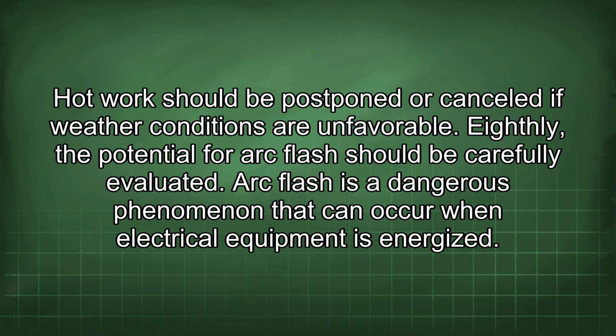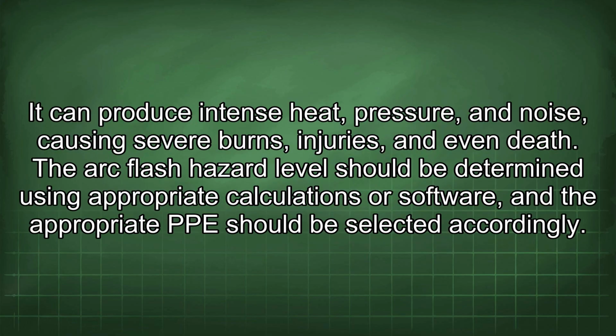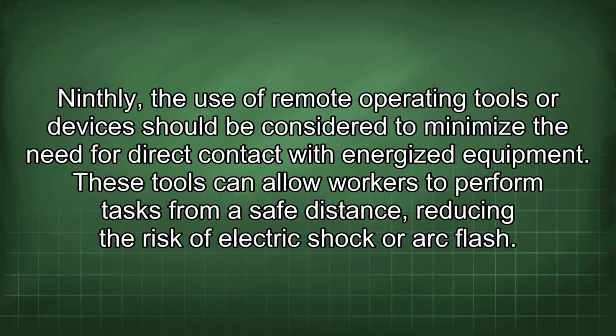Eighthly, the potential for arc flash should be carefully evaluated. Arc flash is a dangerous phenomenon that can occur when electrical equipment is energized. It can produce intense heat, pressure, and noise, causing severe burns, injuries, and even death. The arc flash hazard level should be determined using appropriate calculations or software, and the appropriate PPE should be selected accordingly.